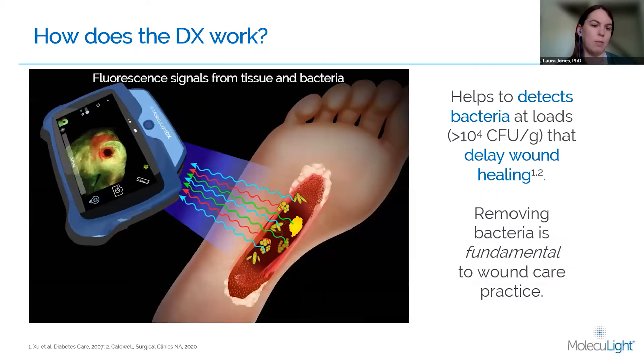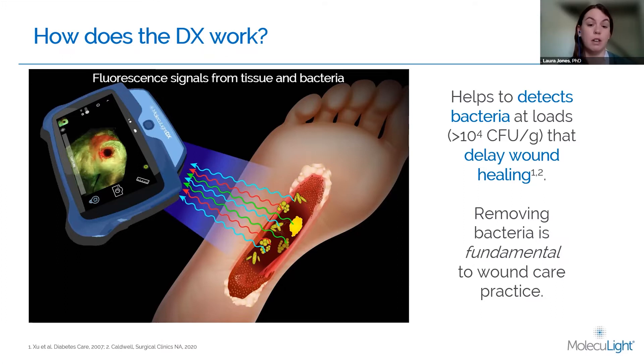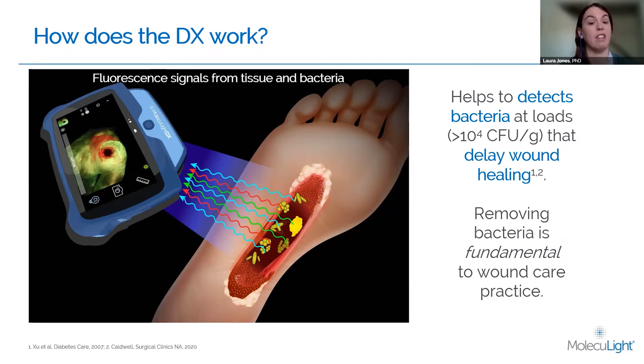The really unique part of the MolecuLight is the fluorescence imaging capability. In a darkened room, you'll use the device to shine a safe violet light onto the wound, and different components will fluoresce different colors. Skin components, slough, anything that's collagen-rich will fluoresce green, while the vast majority of bacteria will fluoresce in the red fluorescence range, indicating elevated bacterial loads. Cyan fluorescence indicates the presence and location of Pseudomonas aeruginosa specifically, so in real time we can identify that specific bacterial species.